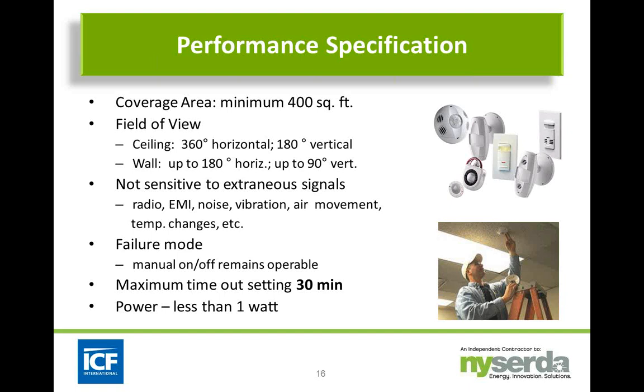If you're talking ceiling mounted, you want to look at a 360-degree horizontal detection space and 180 degrees for vertical. So if you're walking underneath the device, it'll pick you up at 180 degrees from that. For wall-mounted, up to 180 degrees horizontal and up to 90 degrees vertical. You'll notice some of the sensors out there are actually 170 degrees, so they don't pick up the last 5 degrees on either end of the 180-degree wedge.